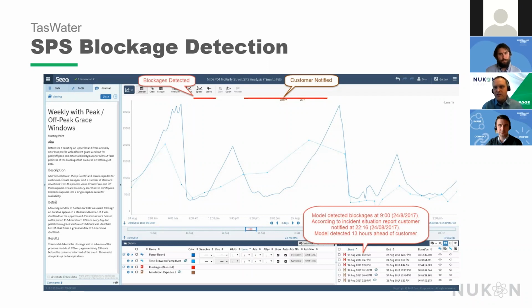This gives you the ability to detect those anomalies upstream from the pump station. Here, the upper bound represents the time limit between pump runs, which is a dynamic limit. When we breach that limit, using some criteria defined in the analysis, we can generate a notification. The red bar at the top there is actually called a capsule — I'll go into more detail in a moment about what capsules are — but we're able to do a number of things when they're generated. For now, you can think of them like a bookmark, a flag to say that an out-of-specification event has occurred, and that can be quite a complex criteria to define.